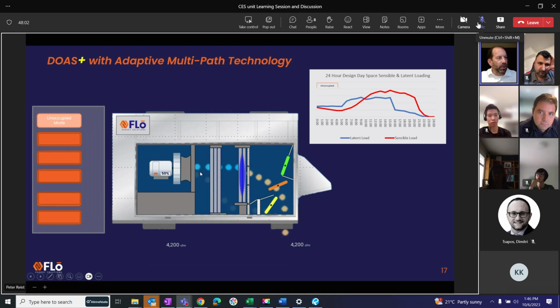So we start off in unoccupied mode. We bring in our return air only. It's coming up over the coil. Maybe the coil's on, maybe it's off, depends what the air needs. We run our fan at half speed because we're just doing recirculation of the store, and that's just cycling that air around. That's that beginning of the day.